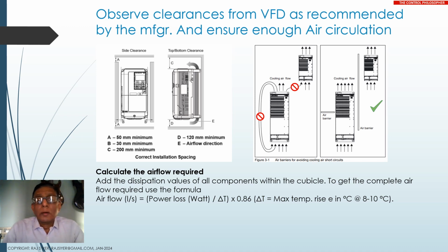Okay, now you see the diagram on the left. This shows installation guidance for a Yaskawa VFD. It shows that 2 inches must be left from the top. B should be from the sides. He wants 30 millimeter minimum, and on the top, he wants 200 mm, that is about 8 inches.